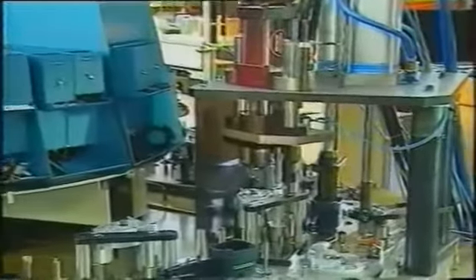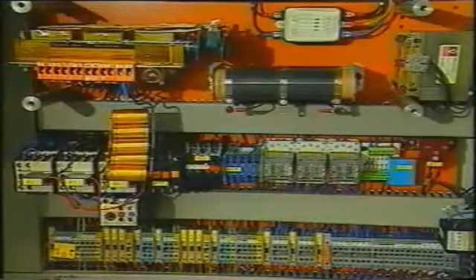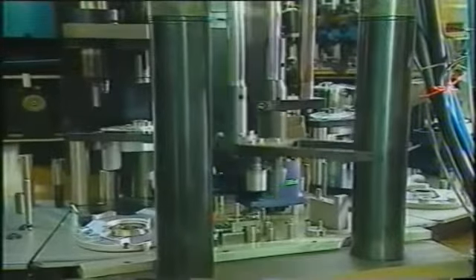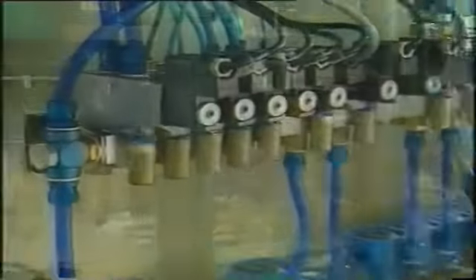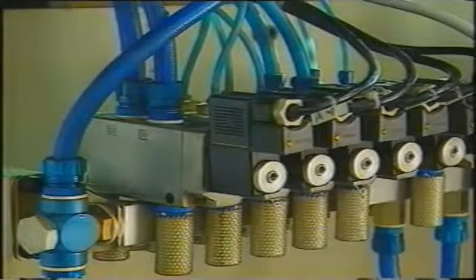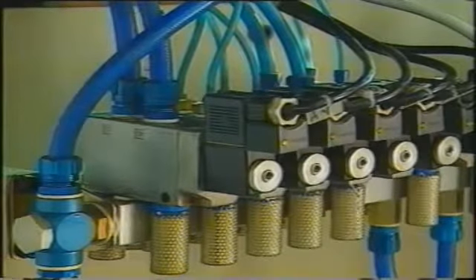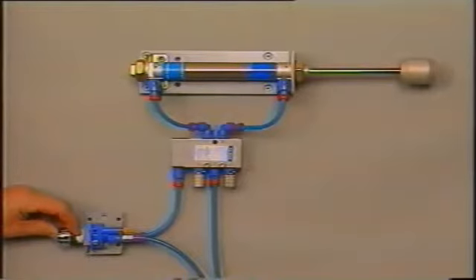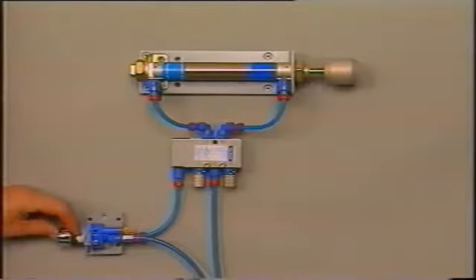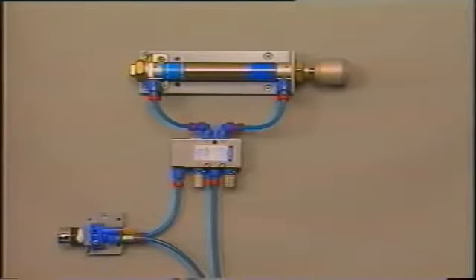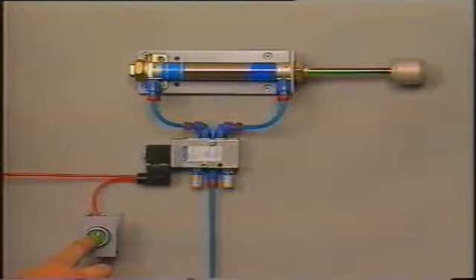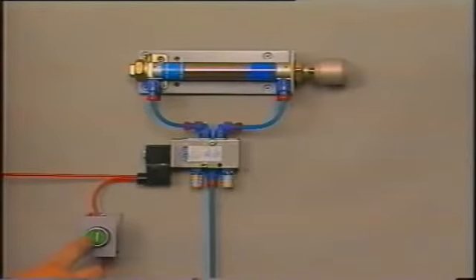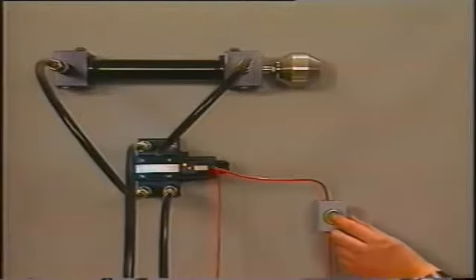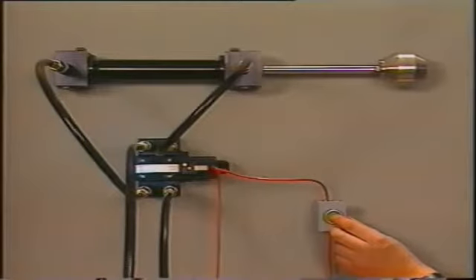In electro-pneumatic and electro-hydraulic systems, the electrical signals in the control part have to be converted into actions by the pneumatic or hydraulic power part. This is achieved with solenoid valves. In their function as final control elements, they are no different to normal pneumatic or hydraulic directional control or way valves. The difference is the way they are actuated. Solenoid valves are electrically controlled, so this is a so-called electro-pneumatic transducer. An electrical signal brings about a pneumatic action. The same in electrohydraulics. An electrical signal is converted into a hydraulic action.